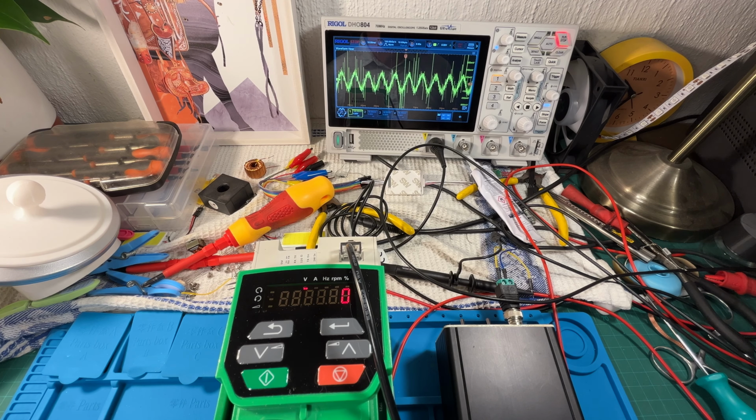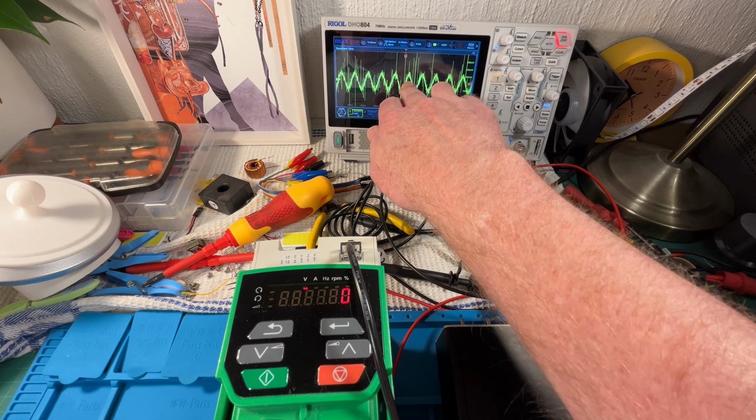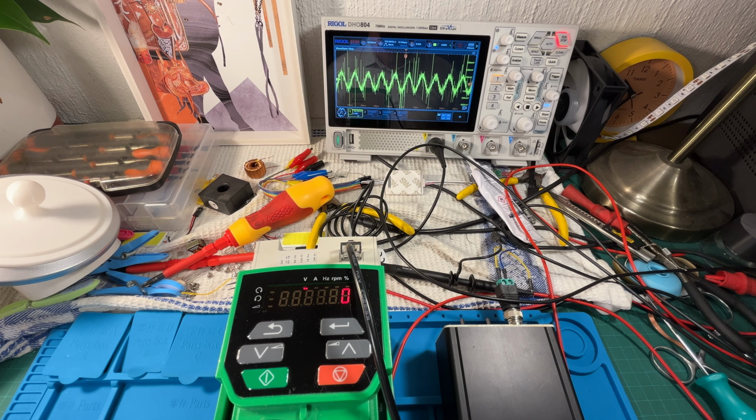So once again, torque decreases as speed increases, so it's constant power. In this case, the same thing, constant voltage, but your current starts to come down, and that's what the current reducing looks like over there. So it's quite normal to do this with induction motors and variable speed drives.